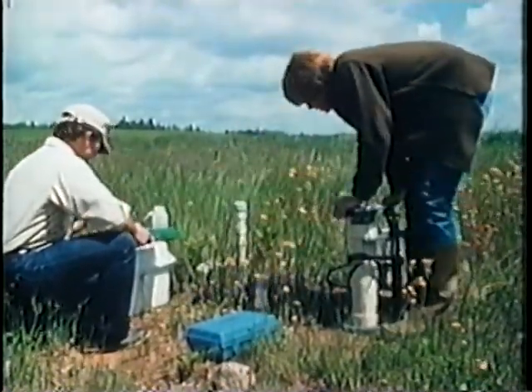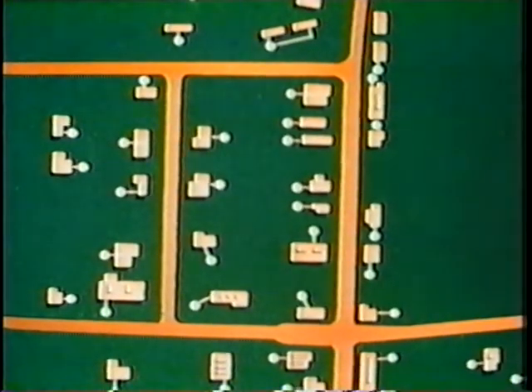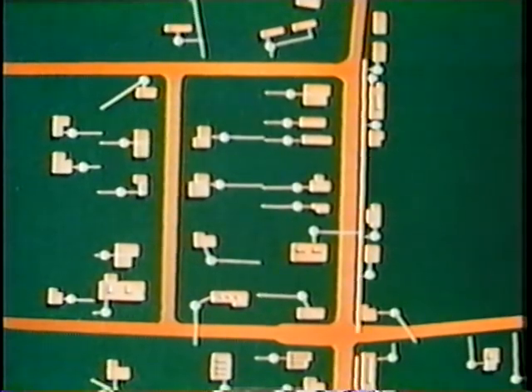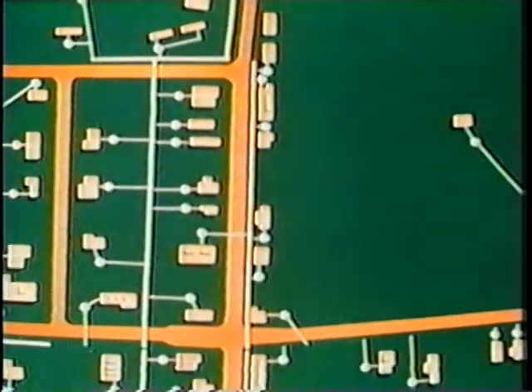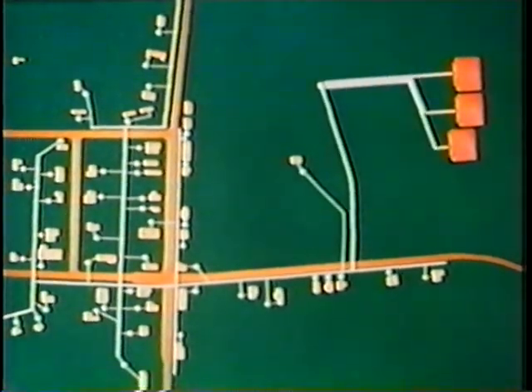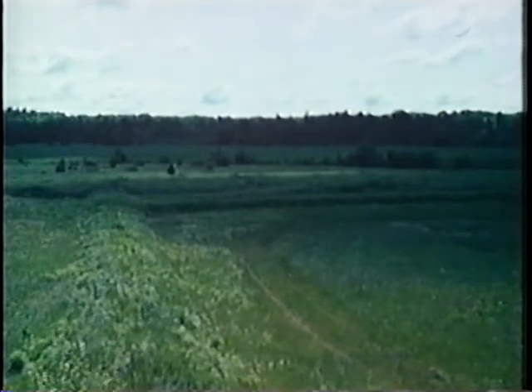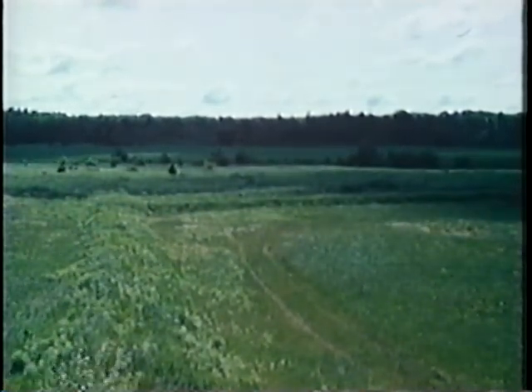Environmental engineer Dick Otis explains: Westboro is a small community of about 80 homes, each of which had been served by individual septic tank systems. Most of these systems were failing, which required the homeowners to upgrade their systems, but the small lots and poor soils prevented them from doing so. The alternative finally selected is a cluster system in which the effluent from individual septic tanks is collected in small diameter gravity sewers. The effluent is then conveyed to one large soil absorption field for treatment and disposal. The district which formed operates and maintains this system, including pumping of each of the individual septic tanks, for a small monthly fee to homeowners.